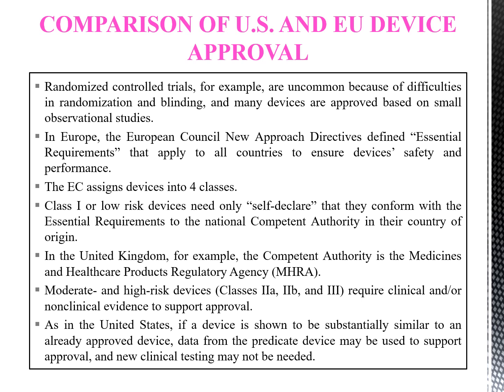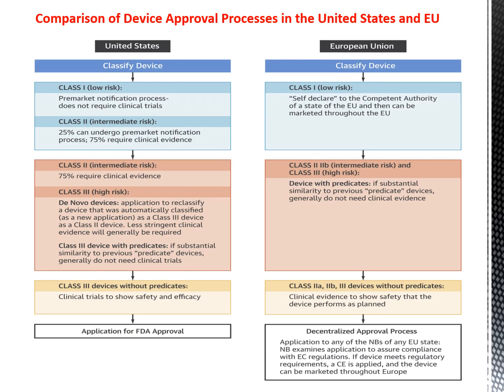And coming to moderate and high risk devices, they require clinical and/or non-clinical evidence to support the approval. As in the United States, if a device is shown to be substantially similar to an already approved device, data from the predicate device may be used to support the approval and new clinical testing may not be needed. Here is the summary of comparison of device approval process in the United States and EU.